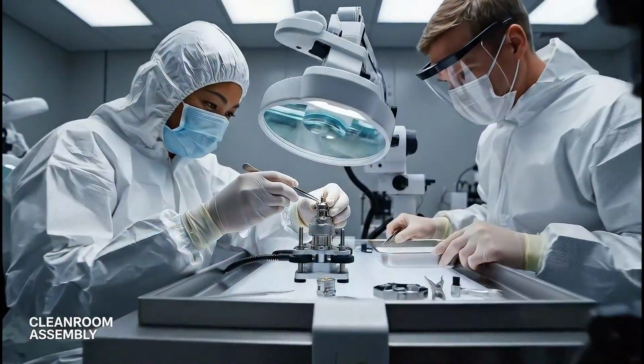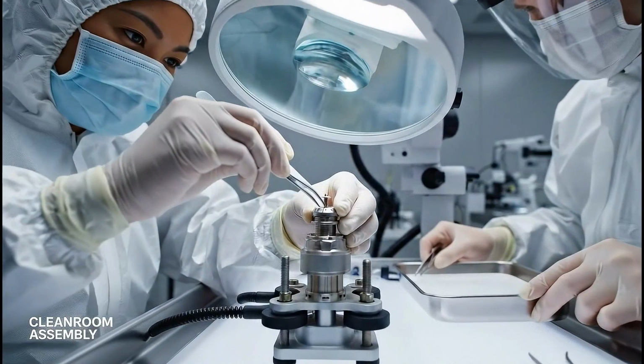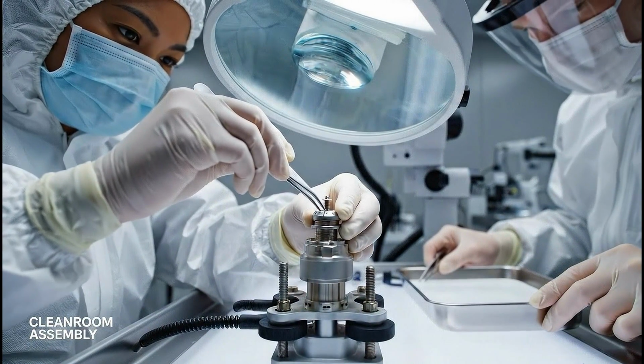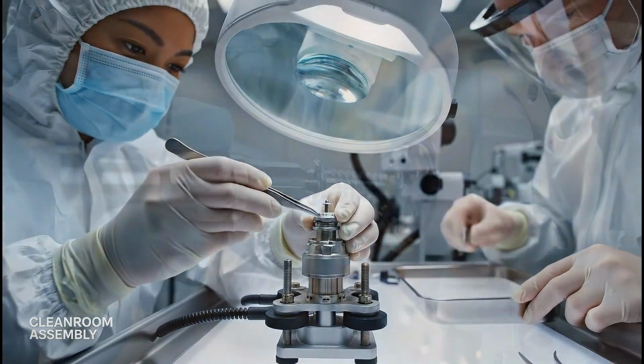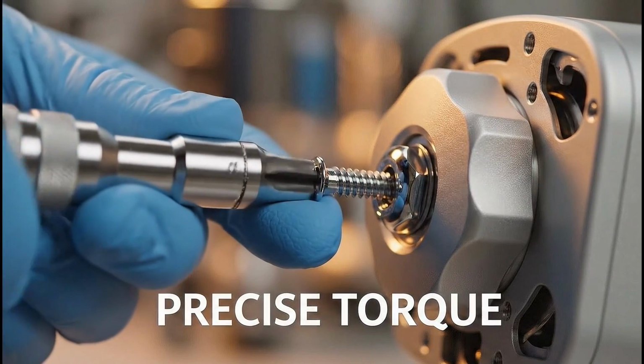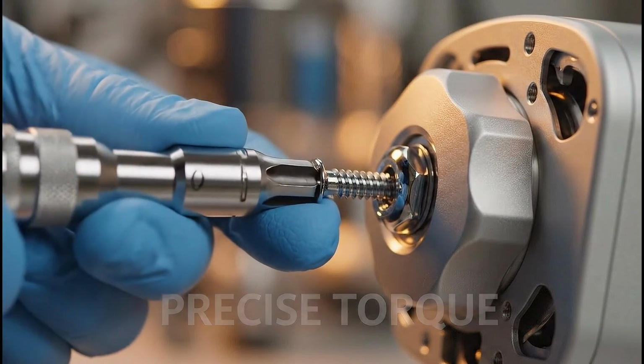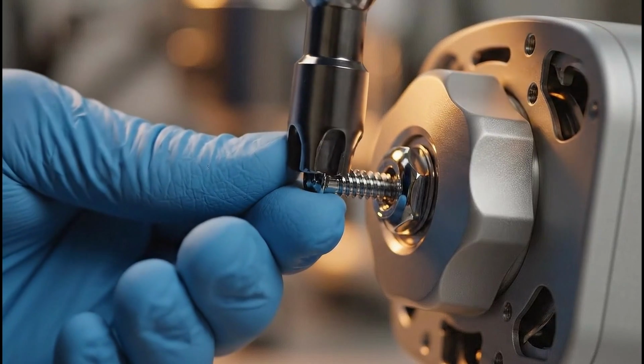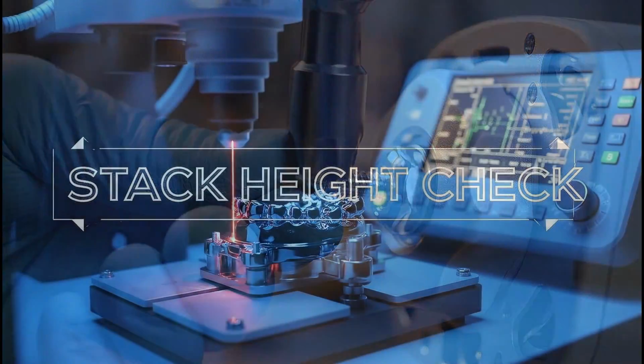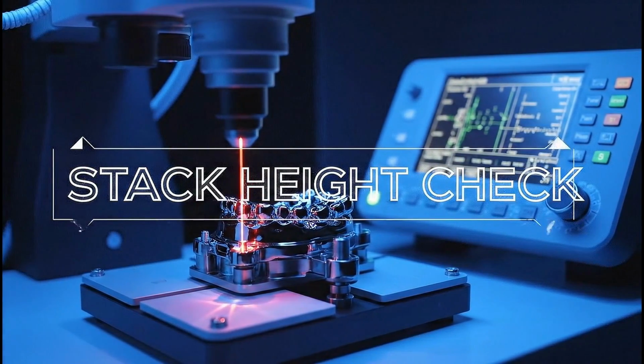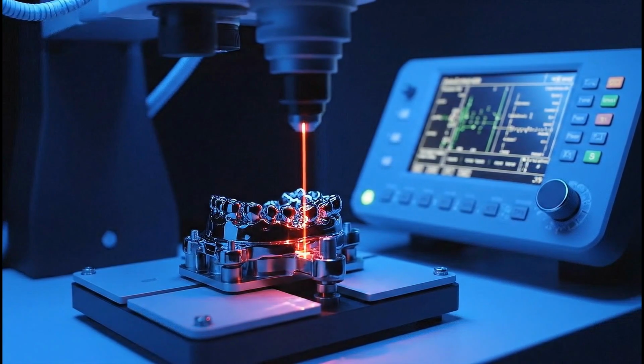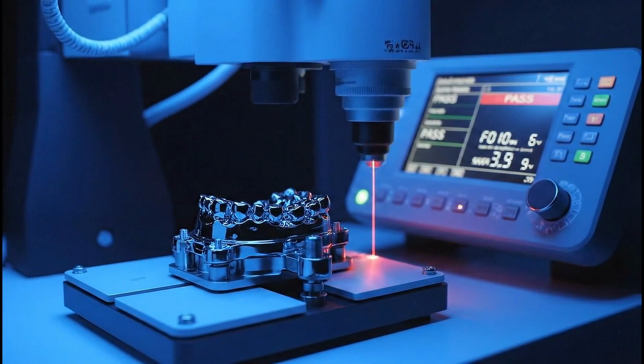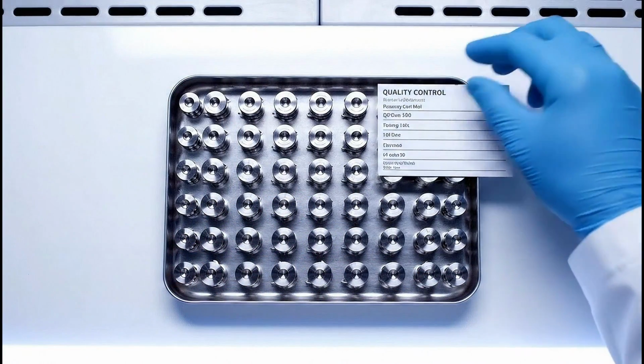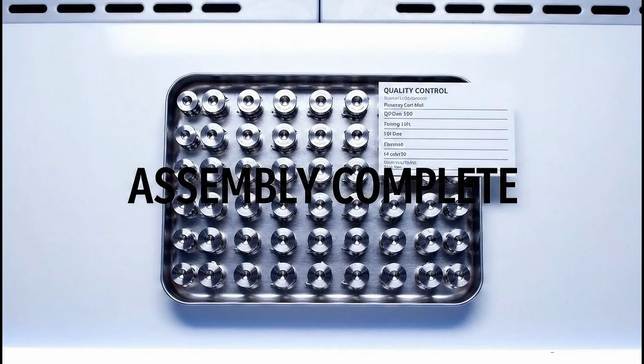The cover screw is hand-assembled onto the fixture. This tiny cap protects the internal threads during the healing phase. We apply a specific torque to ensure the screw stays in place during transport, but is easy for the surgeon to remove. Final dimensional checks verify the assembly stack height. Every millimeter matters in dental restoration. The batch is now fully assembled. But before they can be packaged, they must pass the most rigorous tests of all.